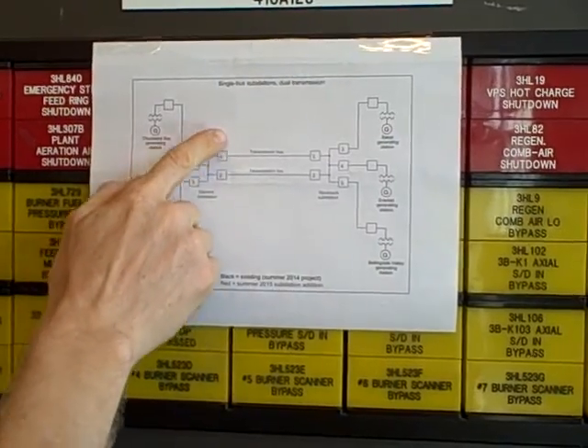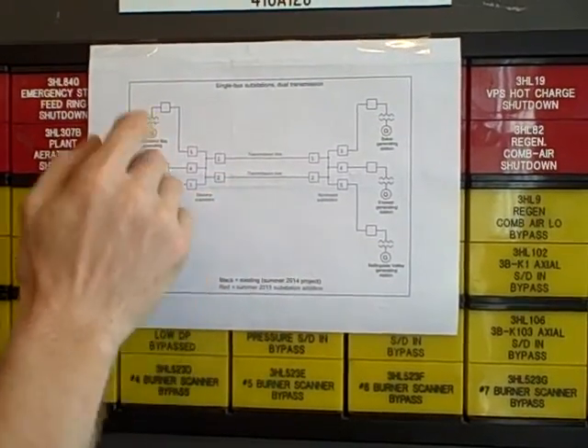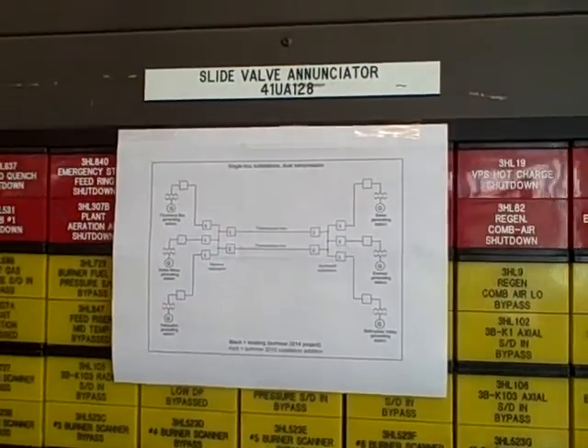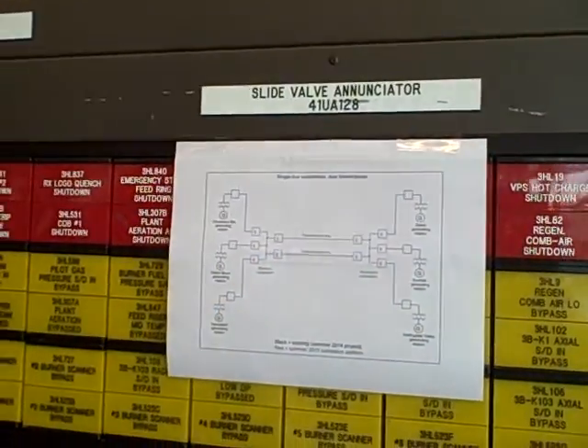Right now all of these breakers on the Stevens substation are open. You can see they're all green — they're all tripped — so the Diablo generator has no way of getting its power to that bus.